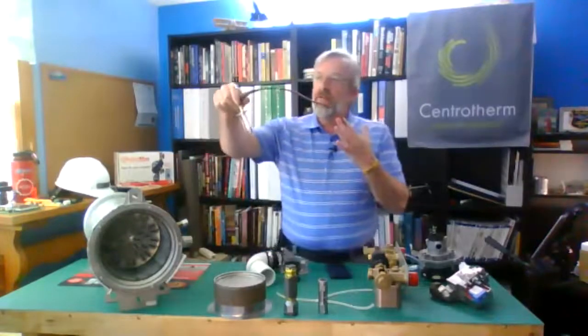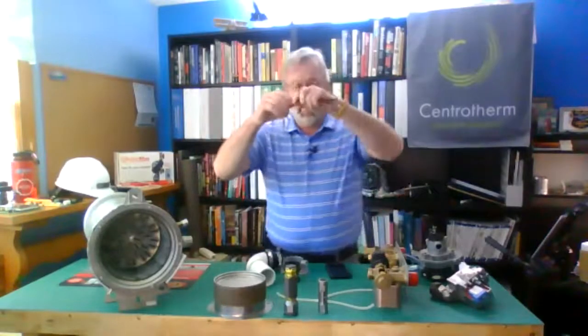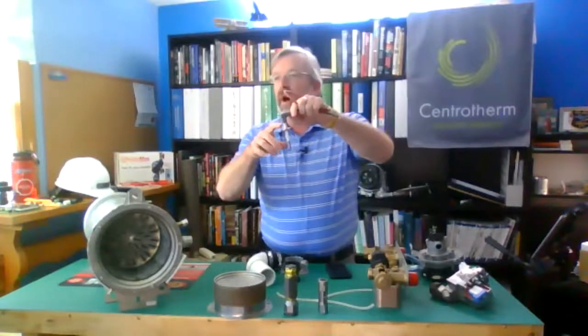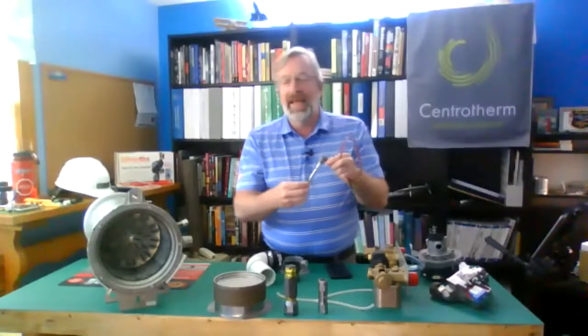And you can go ahead and let your igniter hang outside the cabinet. There's going to be a green ground wire. That green ground wire has to remain attached. The reason is in our ignition circuit, I'm sending voltage down here and it's jumping back to ground. It's how I get that spark. In a sense, it's almost like I'm creating a short.